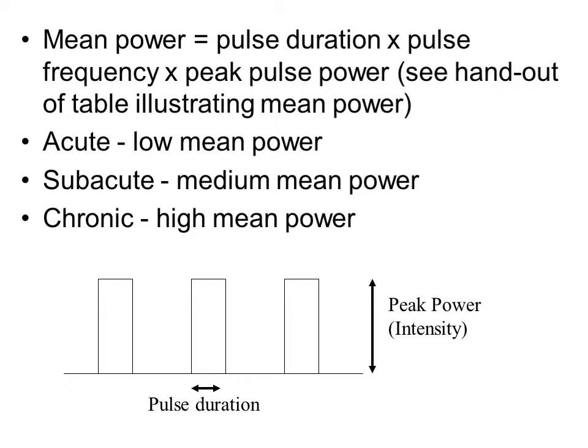The mean power can be calculated on the basis of pulse duration, frequency, and power. You will receive a table giving examples of mean power at different settings in the practical session. Generally speaking, it is good practice to use low mean power with acute injuries, medium mean power with sub-acute, and high mean power with chronic injuries. At all times, the patient's signs and symptoms should determine treatment progression and you should err on the side of caution in the first treatment.